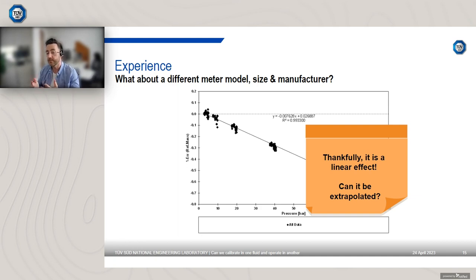Now what people ask is, can it be extrapolated? So can you calibrate a device at, let's say, 10, 20 and 40 bar, derive a pressure compensation factor and then operate at, say, 80 bar or 100 bar, so a slightly different pressure? It's a good question. A lot of people are interested in this because you want to use a meter potentially at different pressures, and if you had to calibrate at each individual pressure, it'd be quite costly, time consuming, and might not be the best use of your time and resources.